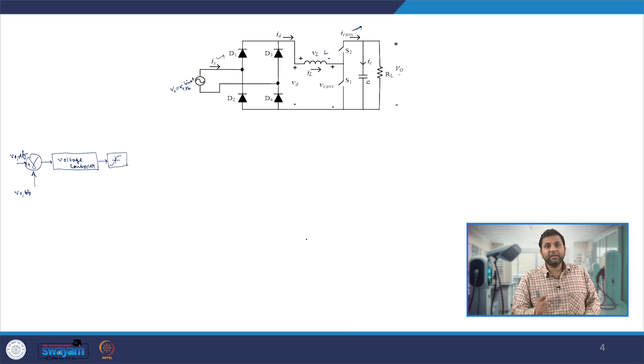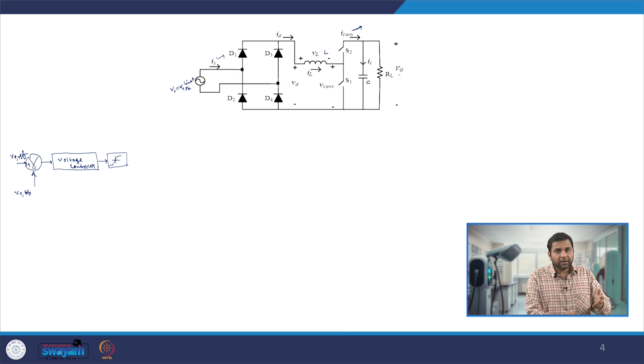Now, let us take one more example. For example, if you want to keep this V naught reference at 400 volt and let us say V naught feedback is at 420 volt, that means one needs to make sure that this capacitor should discharge more and reach that 400 volt mark. Now, to do that, one needs to make sure the energy which is used to charge the capacitor gets reduced, then only we can make sure the capacitor will be discharging more, and that is when the voltage will fall down to 400 volt.